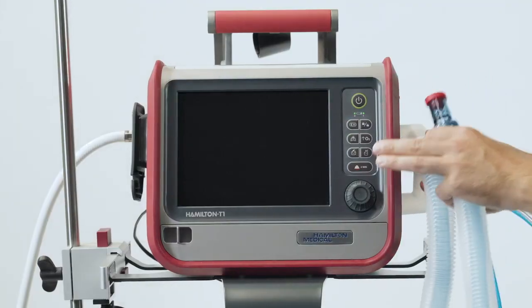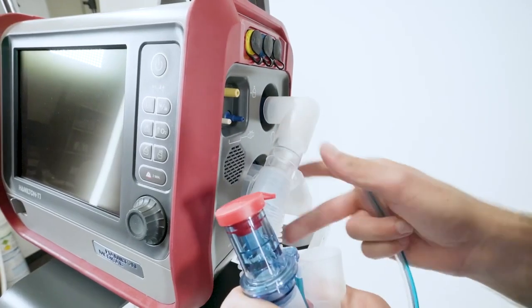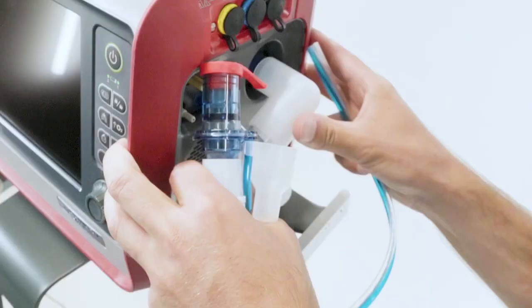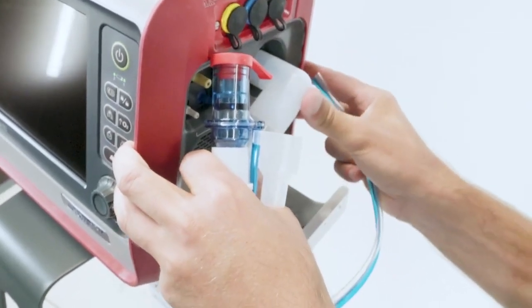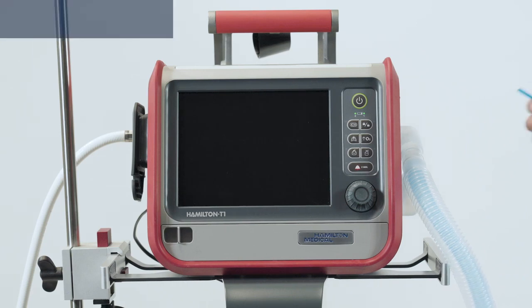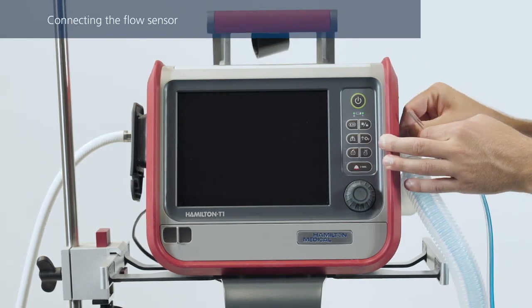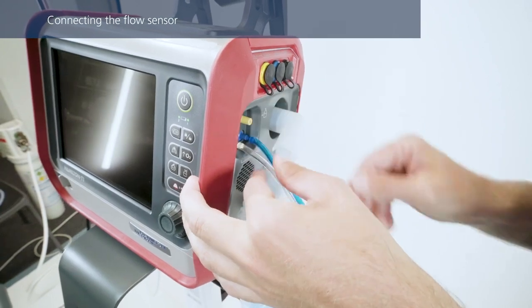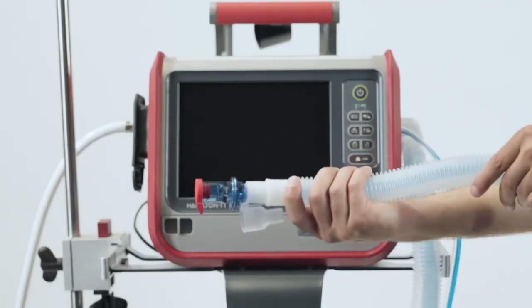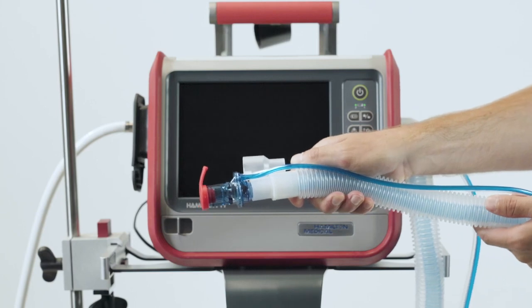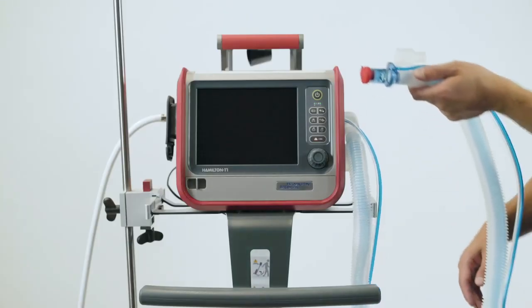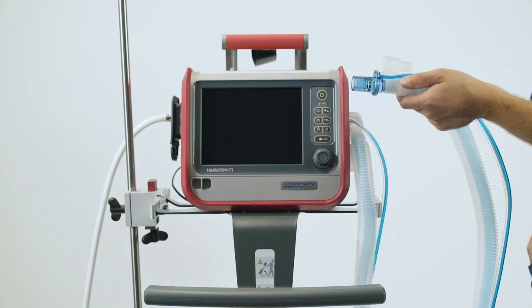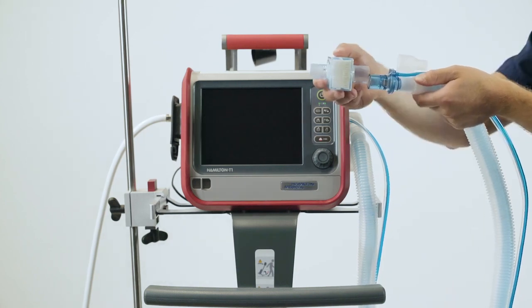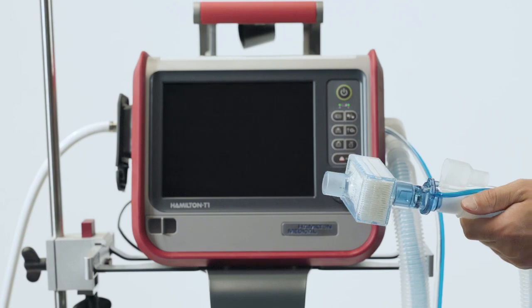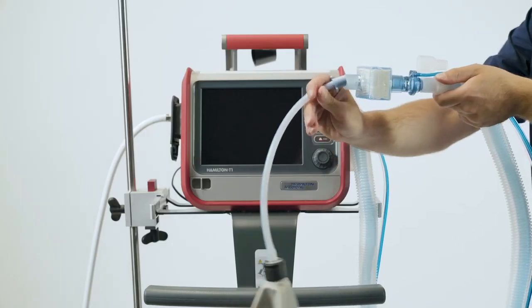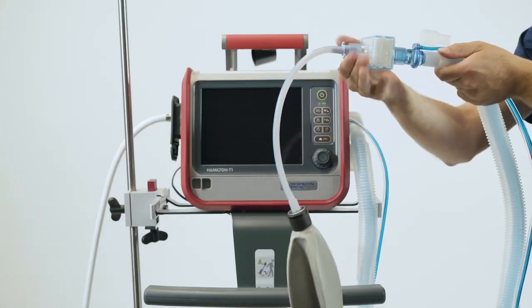To connect the coaxial breathing circuit, firstly attach the main tube to the inspiratory port and then connect the elbow adapter to the expiratory valve. Lastly, attach the blue and clear tubes to the flow sensor connection ports. Make sure you always position the flow sensor tubing on top of the flow sensor. When you ventilate a patient with a coaxial breathing system, you need to use a heat and moisture exchanger filter. This should be placed between the flow sensor and the flex tube, as described in the operator's manual.